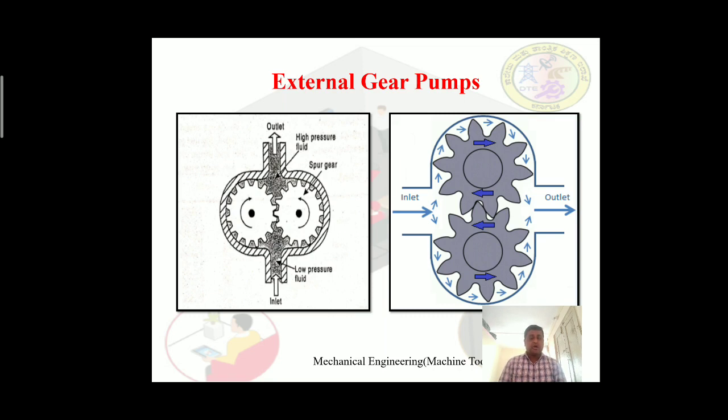When oil is concentrated between the casing and the gear teeth gaps, the oil is trapped there. When it is trapped, the volume decreases and the fluid becomes pressurized. Understood? And then, as the gear rotates, the oil between the teeth is moved from the inlet chamber towards the outlet chamber, and the teeth go into meshing. The volume decreases between the mating teeth, and then fluid is forced out from the outlet.